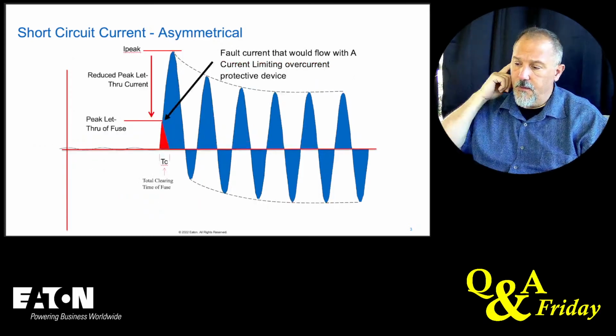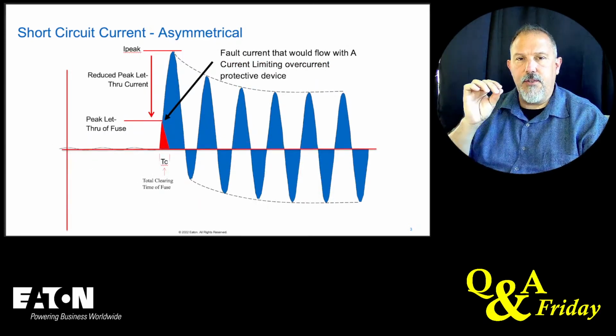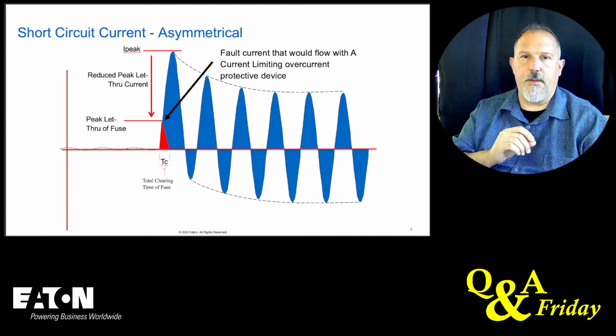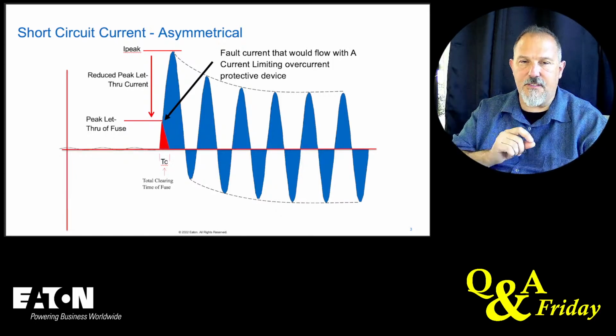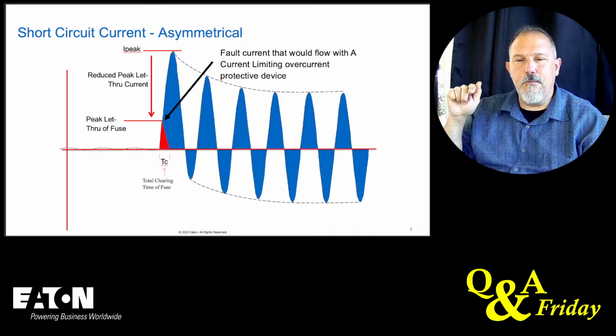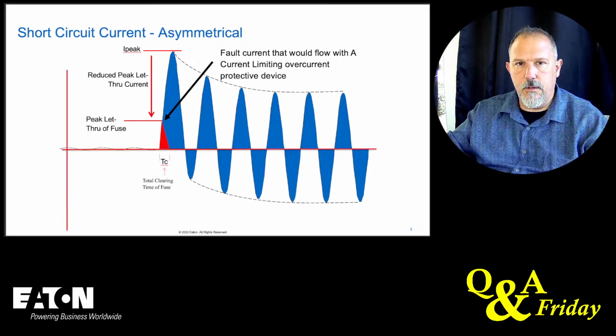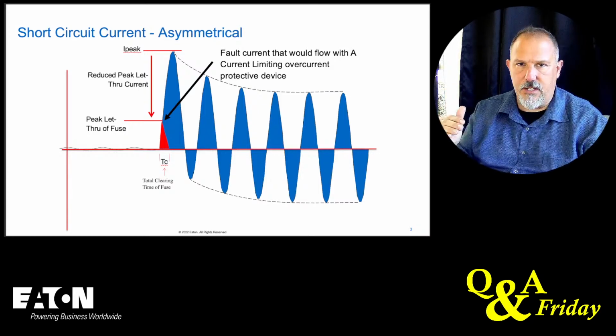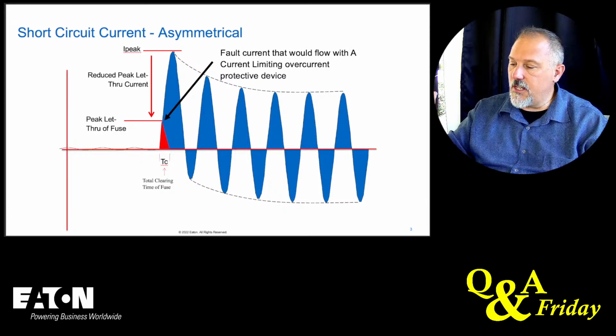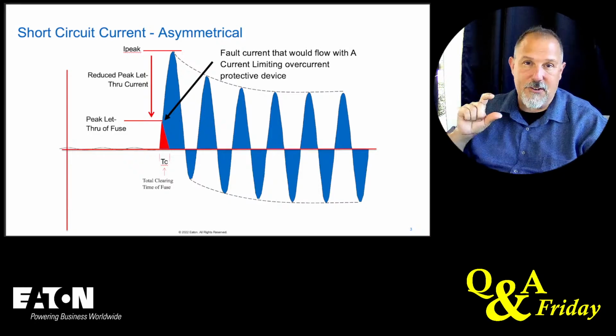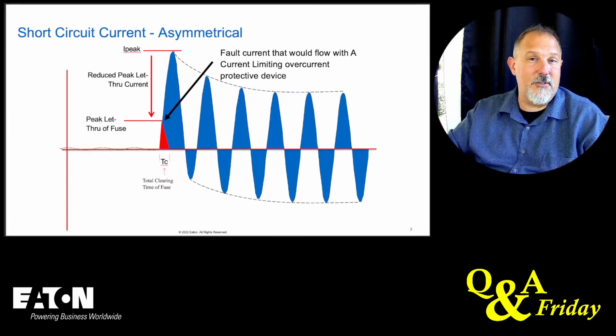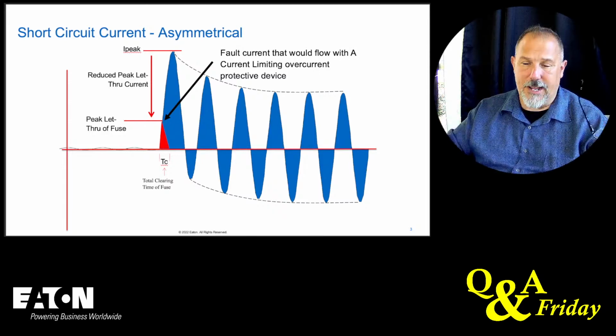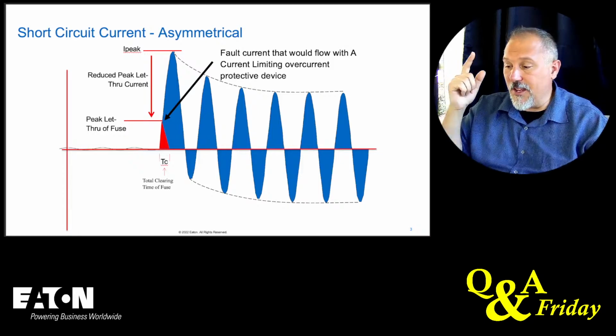But current limitation is the ability of an overcurrent protective device to have a clearing time in less than a half a cycle. So that little red sliver of this entire waveform, if a device clears fast enough within that first half cycle, that's the only energy. Instead of seeing all 6 cycles, the circuit only sees that little red piece of energy. And if I just did the calculation of the area under that trip curve, which is pretty much your amount of energy that you have in that circuit, it's much less. So your operation, now you think about this, okay?